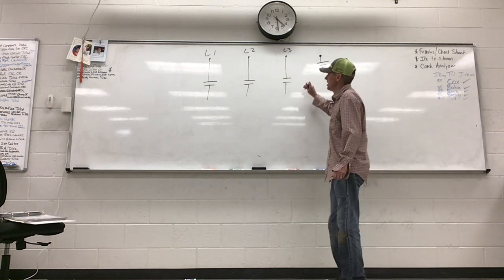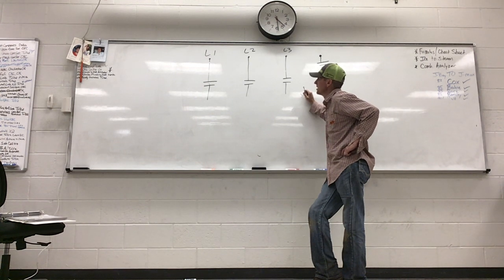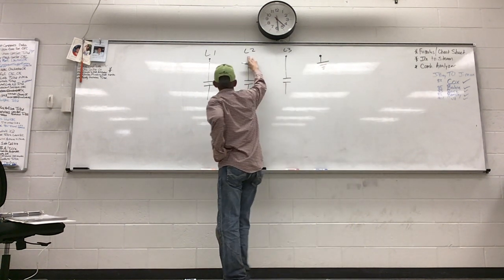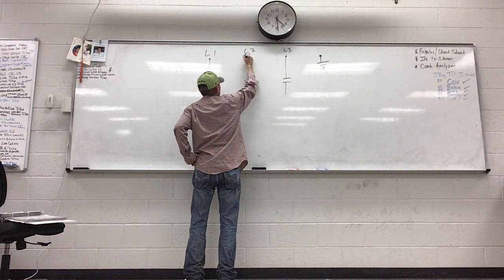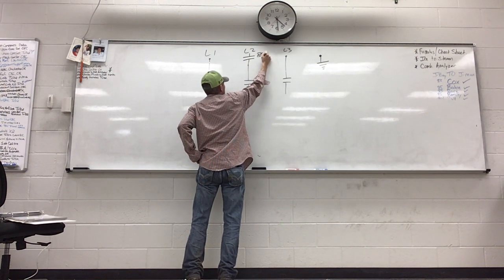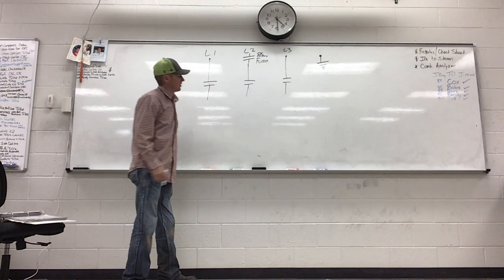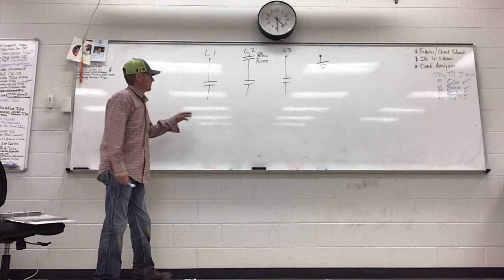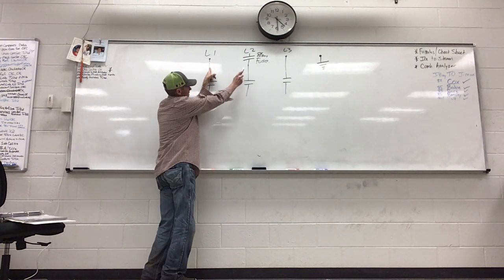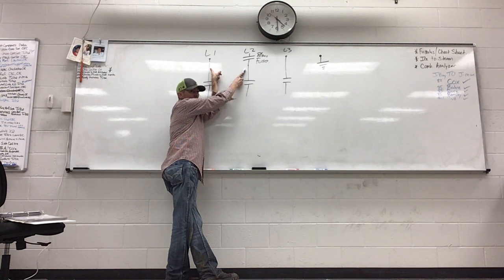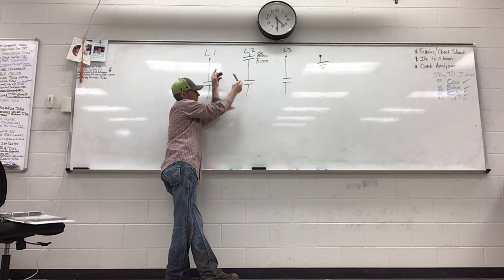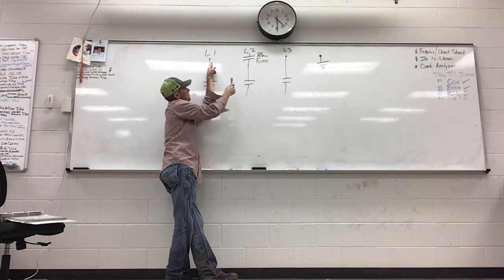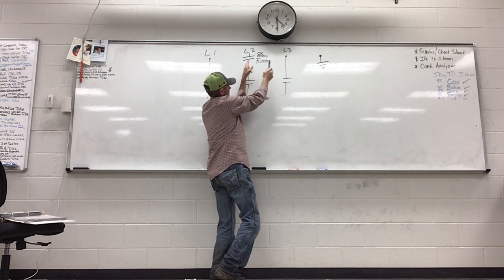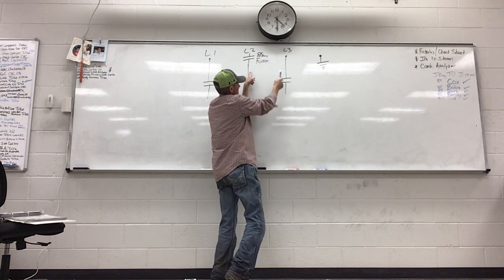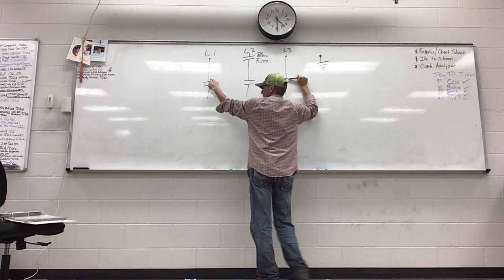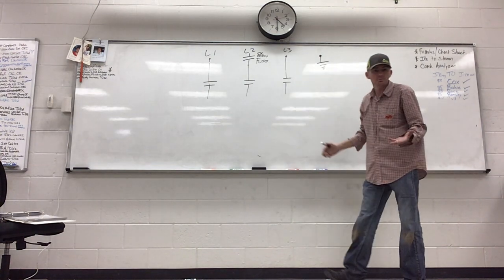I'll get there. So let's say that we lose power. Let's say that L2 blew a fuse. So L2, I'm going to just write blown fuse, even though you probably can't see it, whatever. Okay, so L2 is dead. Now, when I go from 1 to 2, there's no potential difference there. I'm probably going to read 0 volts, right? Probably. If there's nothing else tied in here, we'll talk about that. But between 1 and 2, I'd read 0 potential difference, based off of this drawing. And between 2 and 3, I'd read 0 potential difference. And between 3 and 1, I'd get my full potential, right? So in this building, it'd be 208.